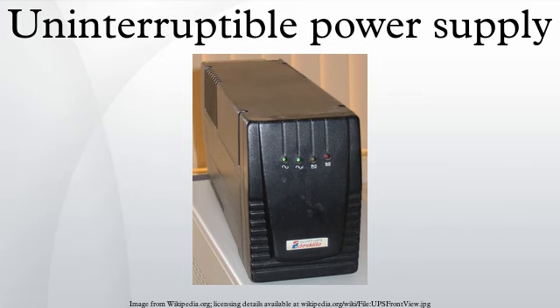Applications. N+1. In large business environments where reliability is of great importance, a single huge UPS can also be a single point of failure that can disrupt many other systems. To provide greater reliability, multiple smaller UPS modules and batteries can be integrated together to provide redundant power protection equivalent to one very large UPS. N+1 means that if the load can be supplied by N modules, the installation will contain N+1 modules. In this way, failure of one module will not impact system operation.